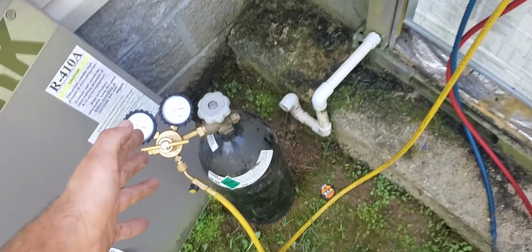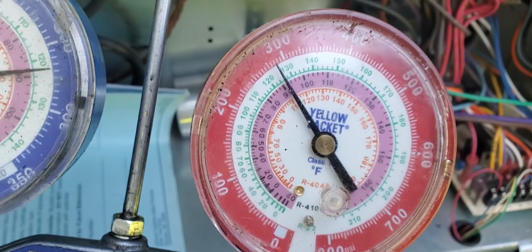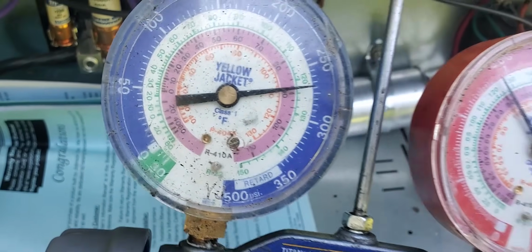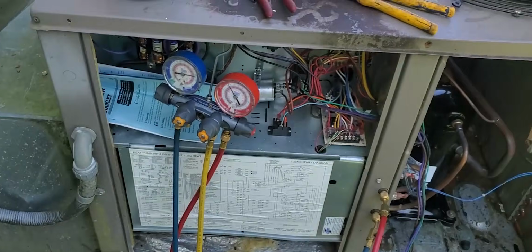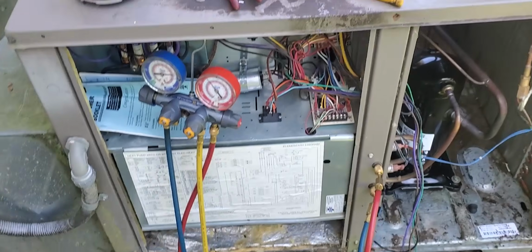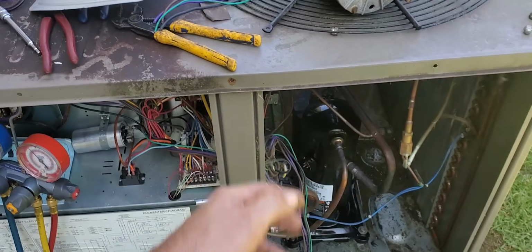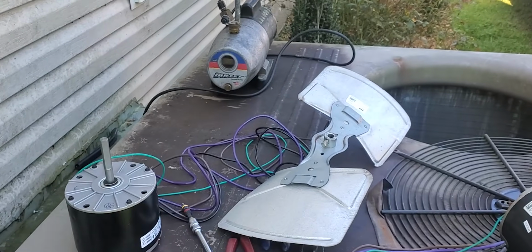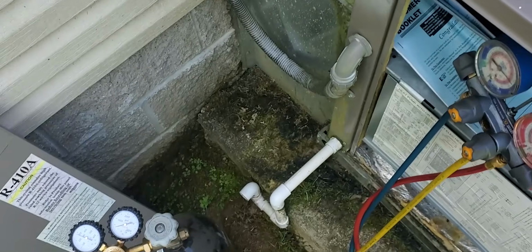So I've got the nitrogen on around 300, high side and low side, and I'm just holding the pressure at 300. That way I can make sure it doesn't leak. You gotta have nitrogen to pressure test and to be able to also remove the non-condensables before you put on the vacuum. So I got the nitrogen on.